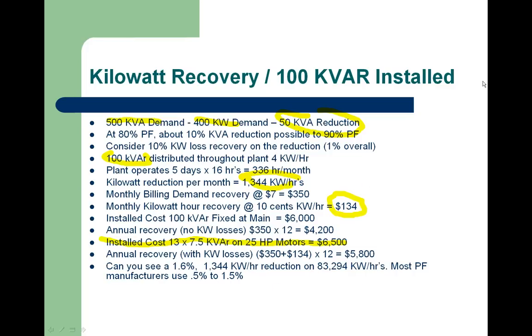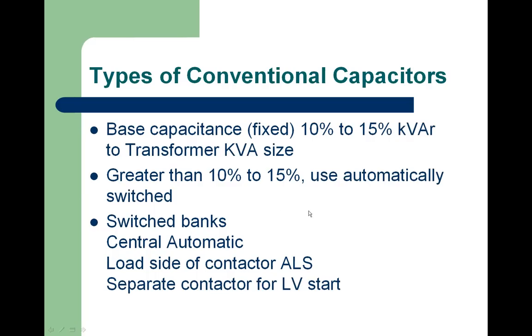Now, that being said, the next slide here is conventional capacitors. So we showed you earlier in the presentation fixed capacitor banks that were up on the wall, and we also had some automatic banks. Typically, to keep the cost down, on both commercial and industrial we generally look at installing somewhere between 10 and 15% kVAR to the transformer kVA size.